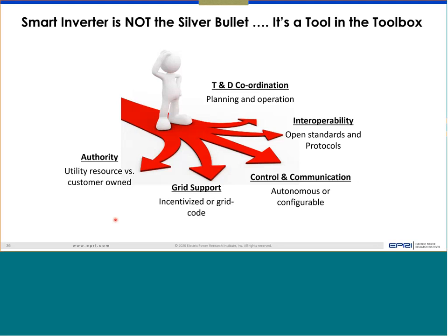So what is the mechanism for that? Authority: in most cases, those assets are not owned by the utility, so what authority do you have to use those resources? Some sort of agreement, as part of your DER interconnection, has to be there, so that you can change power factor and activate certain functionality. That has to be embedded in your contract, otherwise you don't have any authority. Those have to be part of the discussion and planned accordingly. So even if you are not using 1547 right now, maybe in 2 years, you need to start planning right now. So that's my last slide.